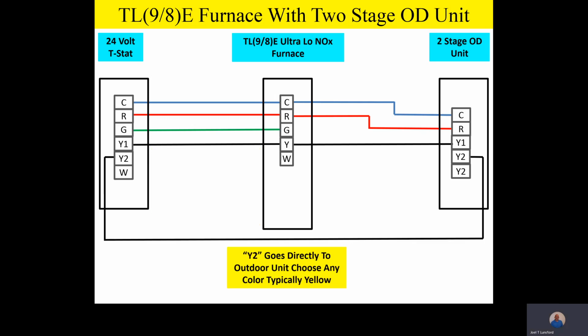Y2 from the thermostat is going to go directly outside. Now, team, watch this. It doesn't even touch the indoor control board at all. So Y2 from the thermostat goes straight outside. Now choose any color you like on that thermostat wire, but typically we find that most contractors on that Y2 or that high-speed cooling call, they're going to typically choose a yellow wire for the high speed.